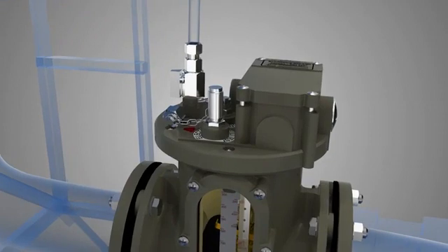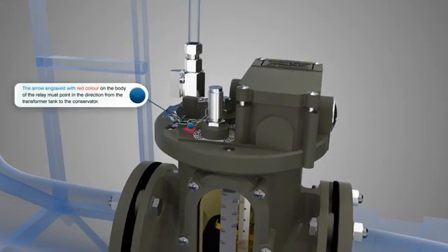When mounting, the arrow engraved with red color on the body of the relay must point in the direction from the transformer tank to the conservator.